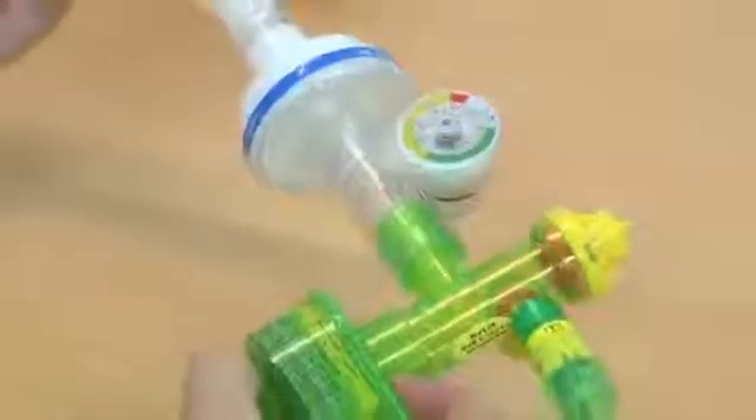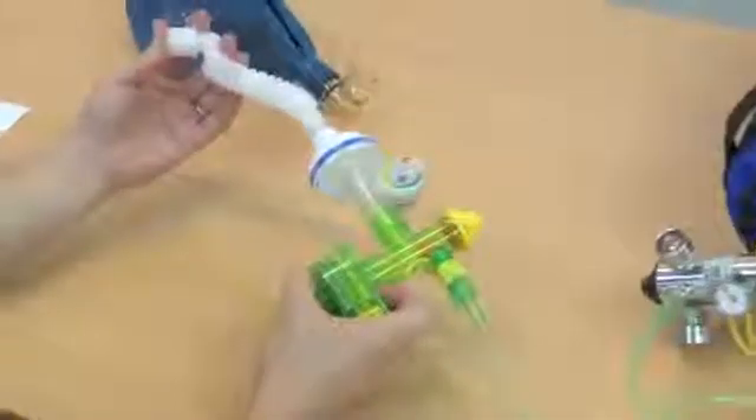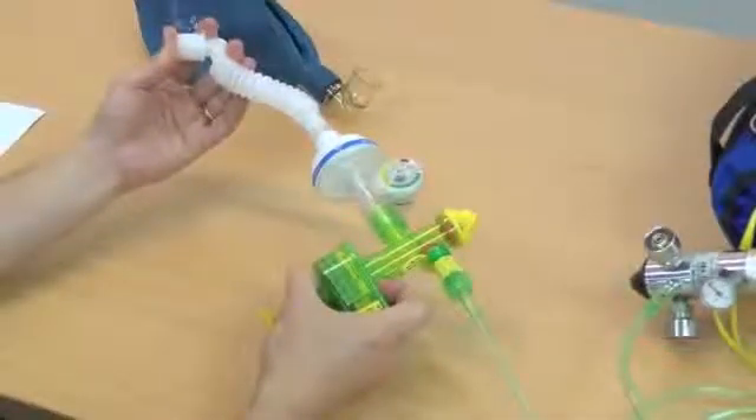If the pressure over-limit safety pop-off valve is triggered, the dial flicks back and forth rapidly. You should then immediately check for kinks or obstruction, or patient factors such as tension pneumothorax. If in doubt, return to self-inflating bag ventilation whilst troubleshooting.